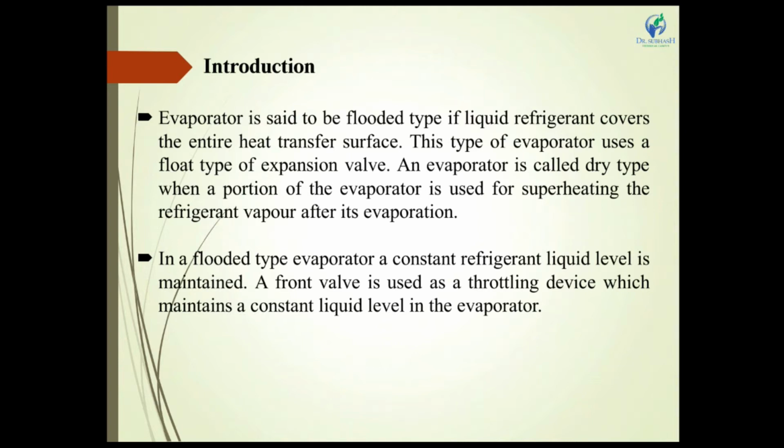Phase change means liquid refrigerant changing to vapor refrigerant at latent heat. More and more heat is absorbed as the liquid refrigerant converts into vapor form. Vapor refrigerant does not absorb heat as effectively as liquid refrigerant, so only liquid must pass through the evaporator. The flooded type evaporator maintains a constant liquid level in the chamber and only liquid passes through the evaporator, for maximum efficiency gain.